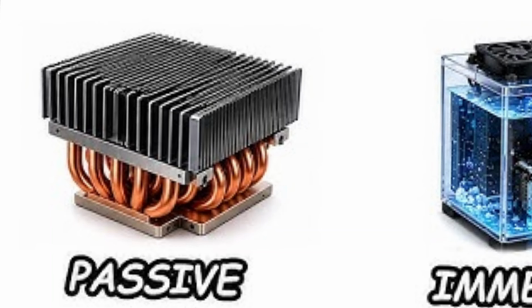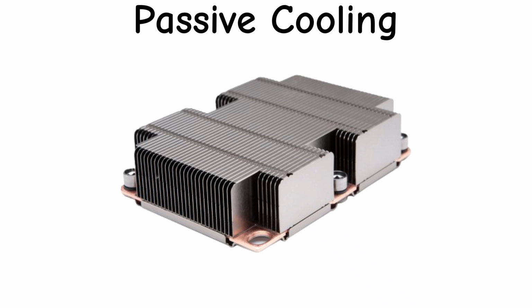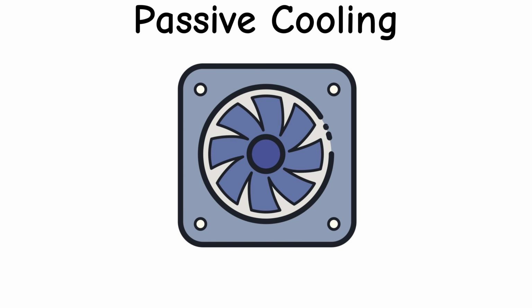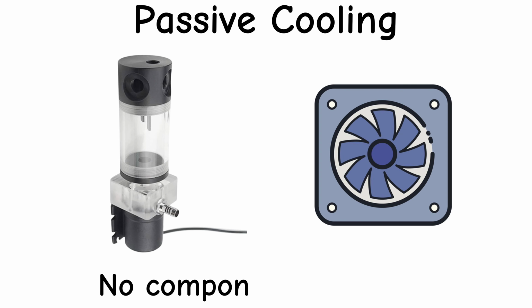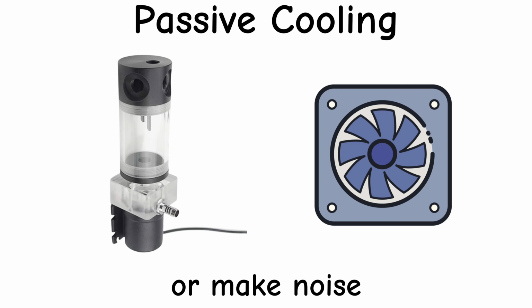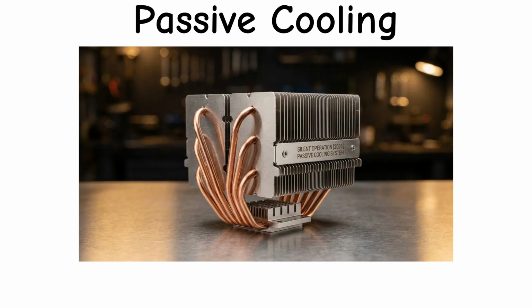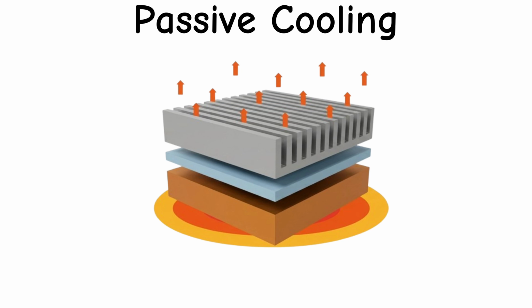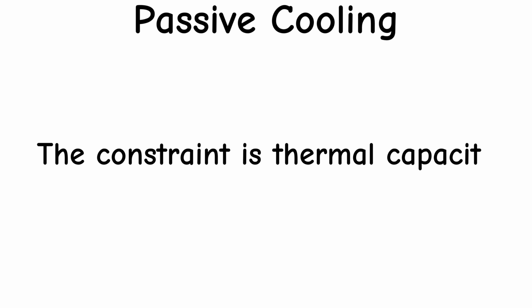Passive cooling. Passive cooling removes every moving part from the thermal equation. No fans, no pumps, no components that spin, wear out, or make noise. Heat moves through metal fins and carefully designed heat sinks by conduction and natural convection alone. The processor warms the metal. The metal radiates that heat into the surrounding air. Silence is the result. The constraint is thermal capacity.